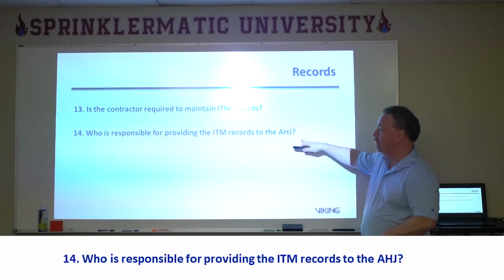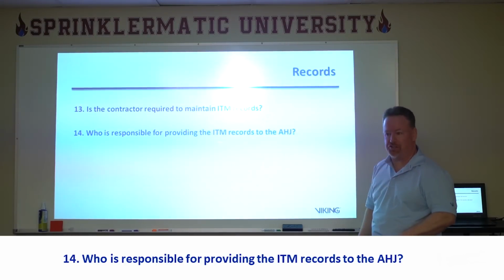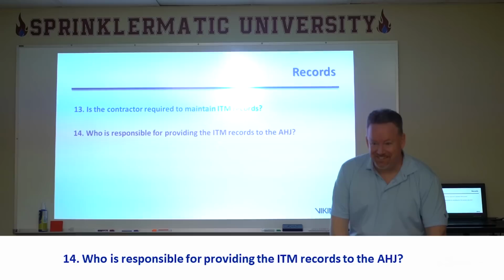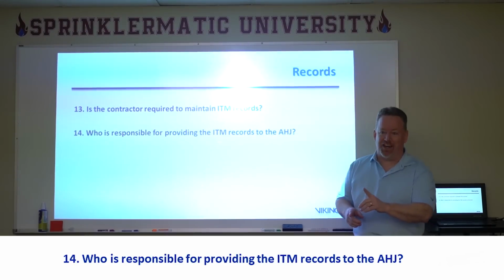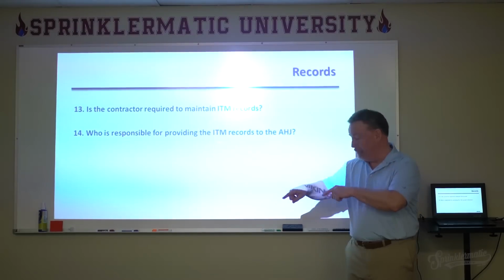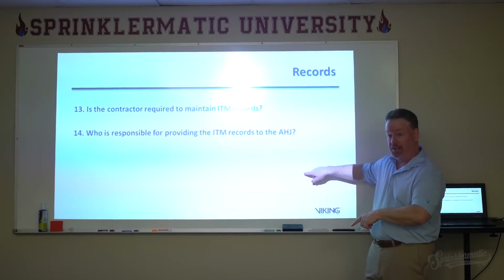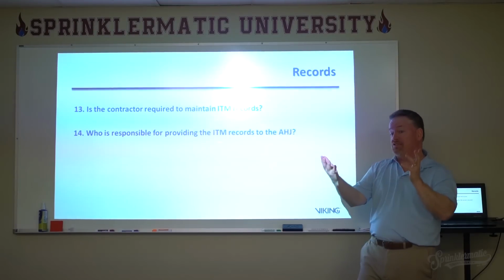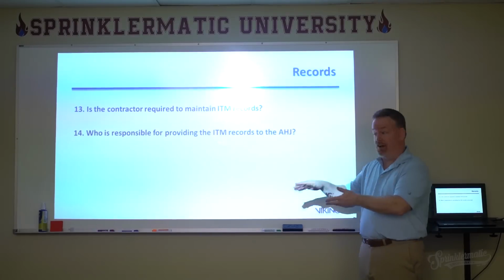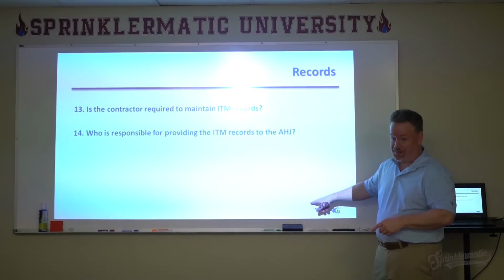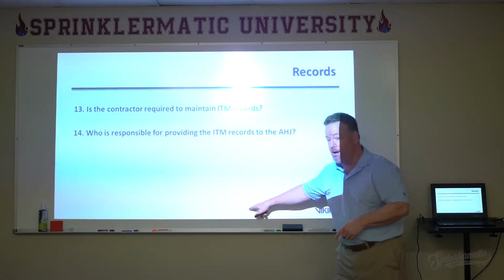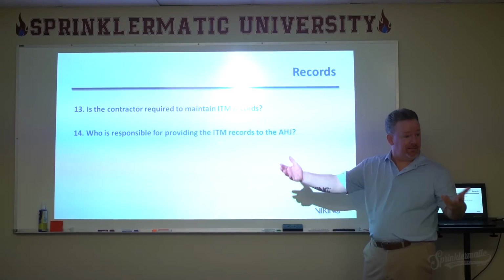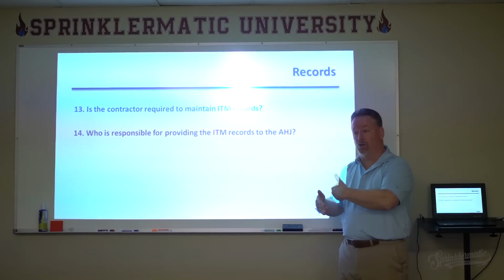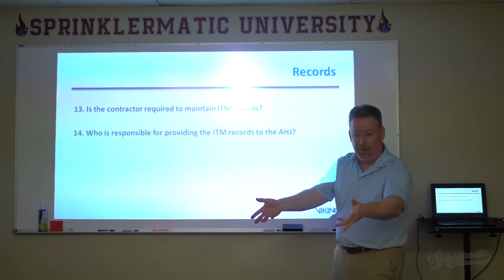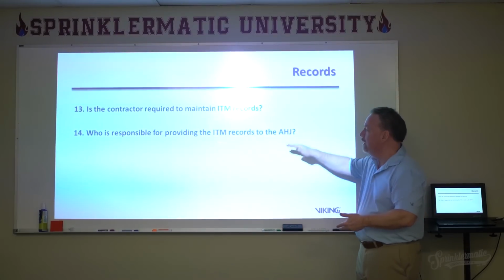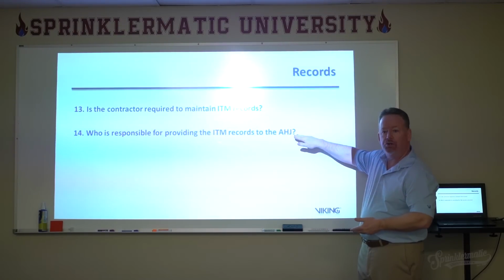Who's responsible for providing the ITM records to the authority having jurisdiction? The owner, by NFPA 25. Remember I talked about earlier when we drew that triangle, we said the owner, but then the real answer is it depends. Because in Florida, also, the inspection contractor is. In the state of New York, no. Up in Georgia, no. It depends on the location and what the state or local regulations are about submitting those records. In accordance with NFPA 25, the owner owns the records.